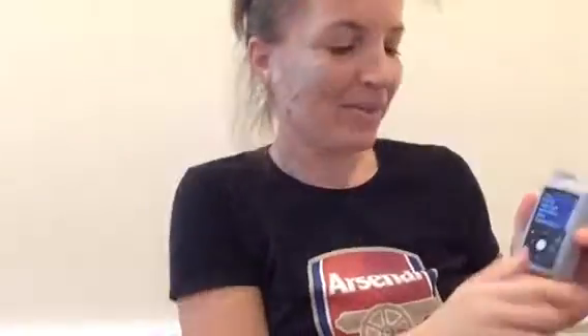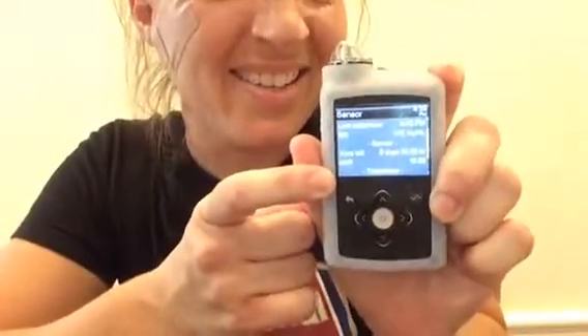Okay, so in order to get your calibration number, the first thing you need is a current blood glucose value. So I'm going to do this fast. And while I get my number up here, I'm going to show you where to locate it. 115, that's my blood sugar right now. That's awesome. Oh, and my number here, my BG, is a 122. So I'm going down to my status. That was main menu. I'm going to my status, and I'm going down to sensor, and I'm going down to ISIG. My ISIG is a 19.99.